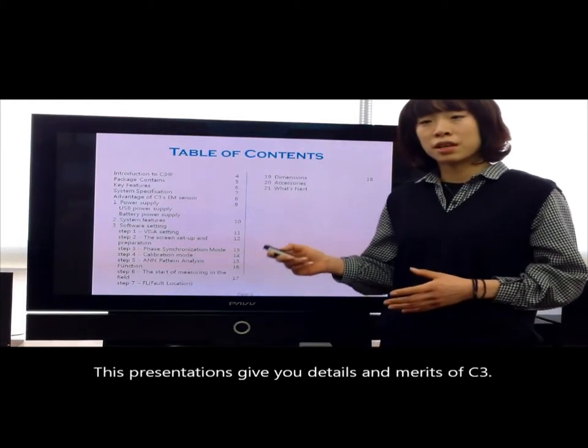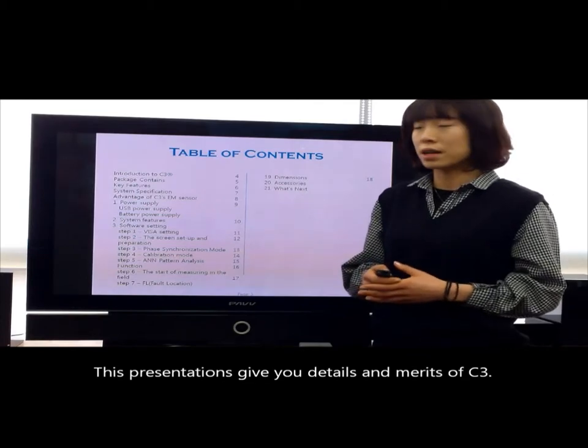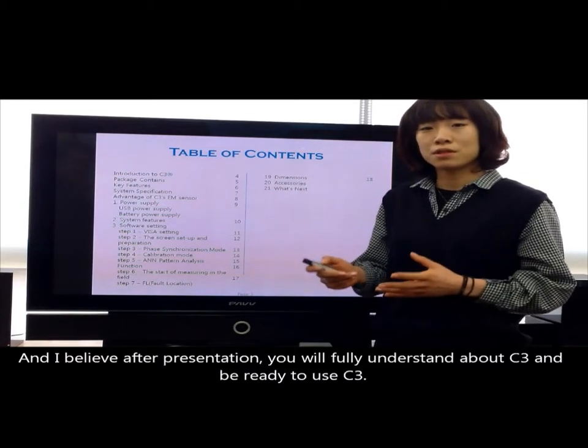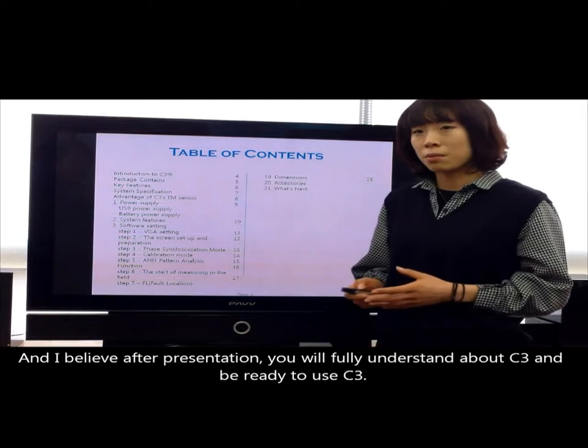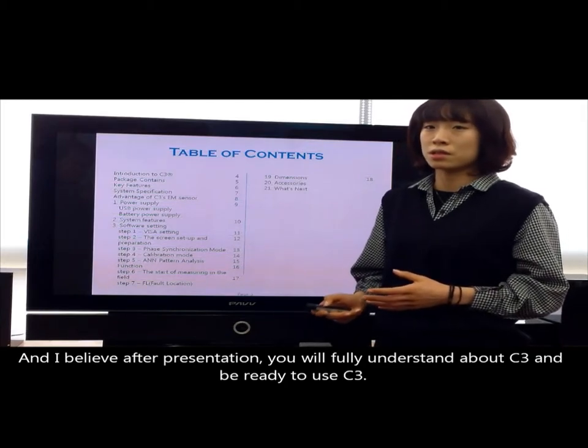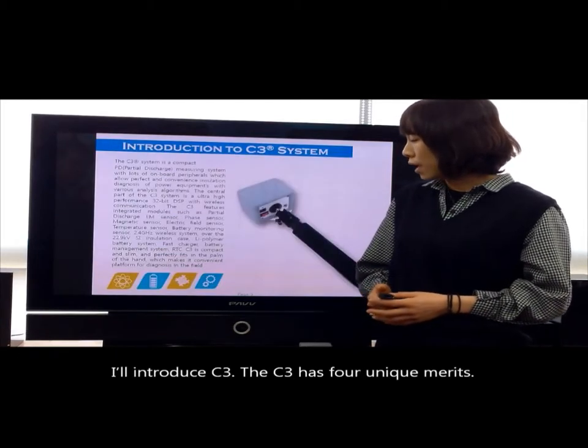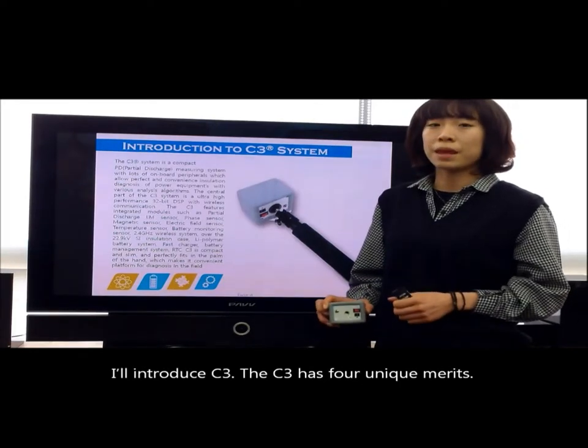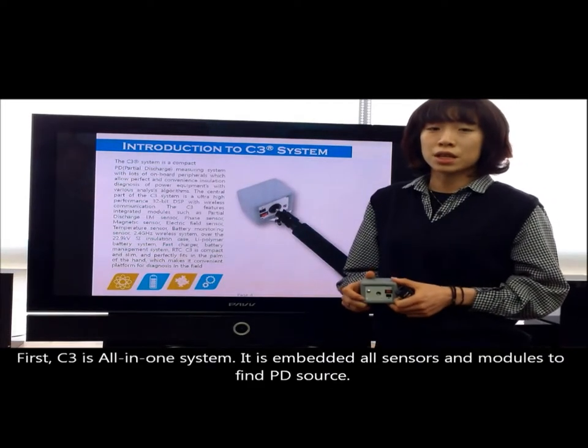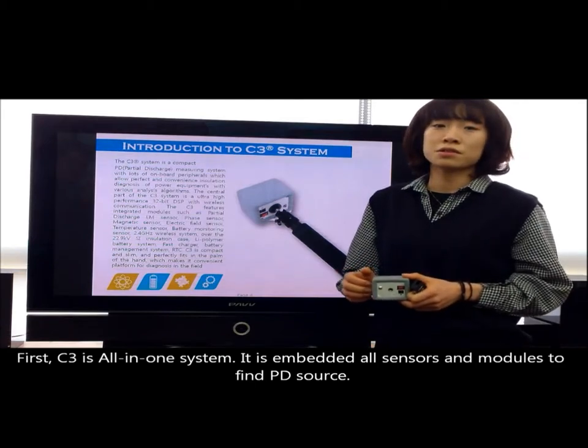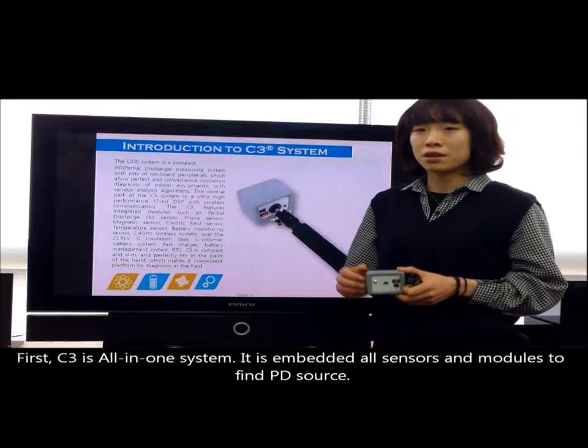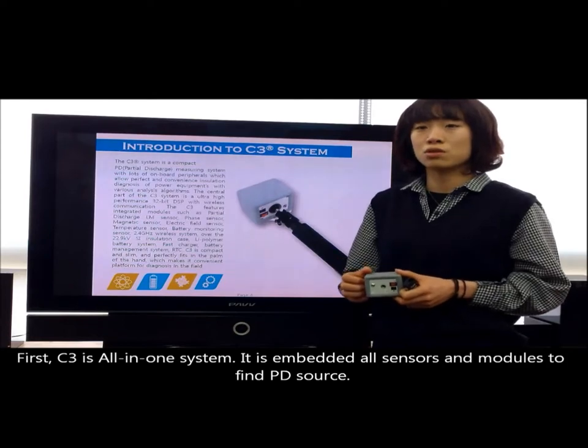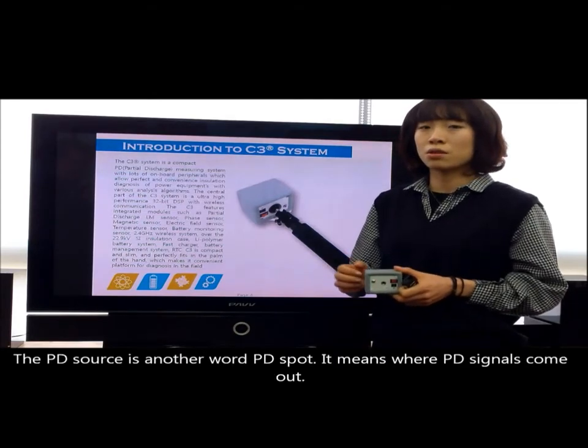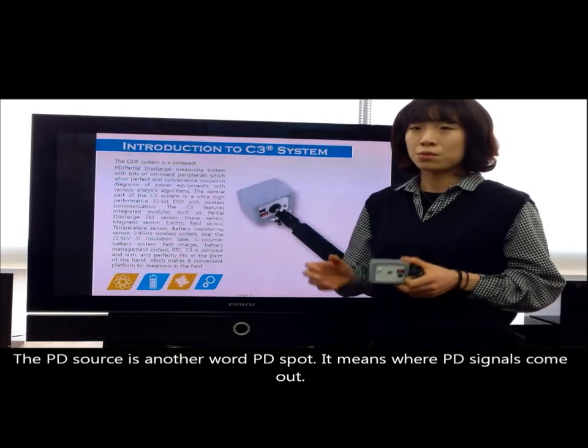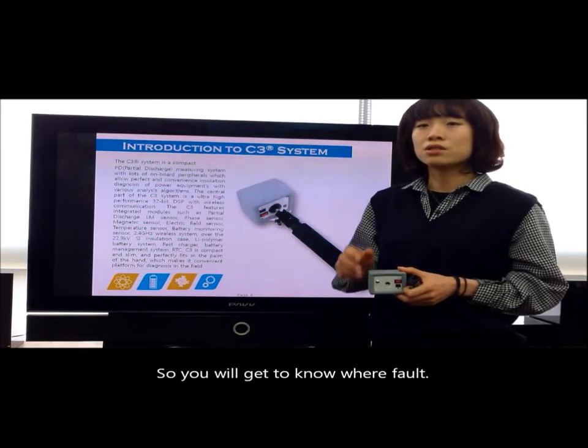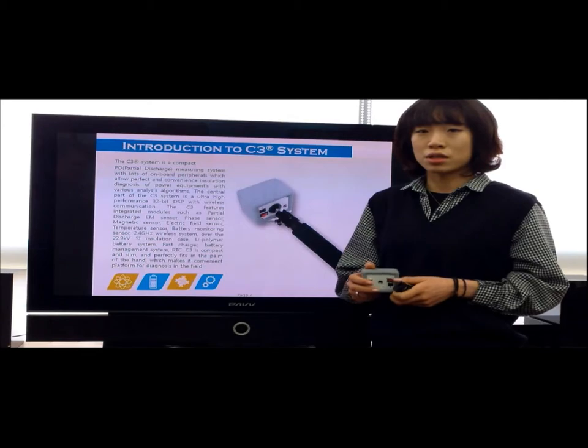This presentation gives you details and merits of C3, and I believe after the presentation you will fully understand C3 and be ready to use C3. And I introduce C3. C3 has 4 unique merits. First, C3 is an all-in-one system. It has all sensors and modules embedded to find the PD source. The PD source is another word for PD spot. It means where PD signals come out, so you will get to know where the fault is.